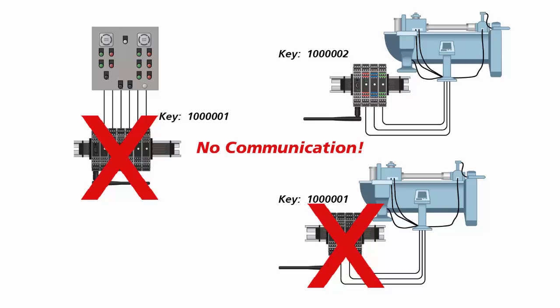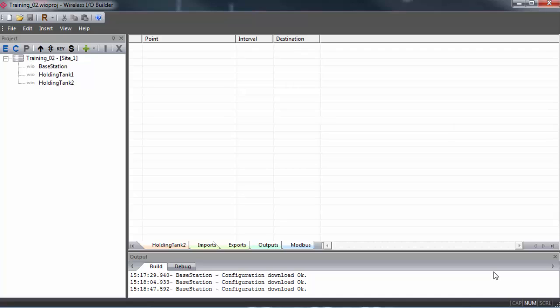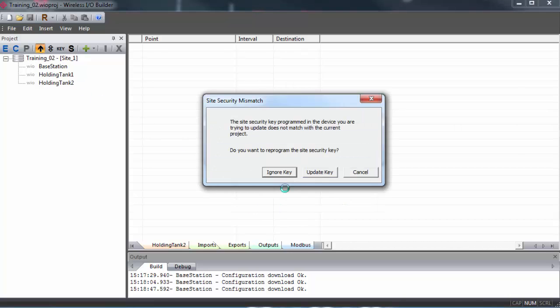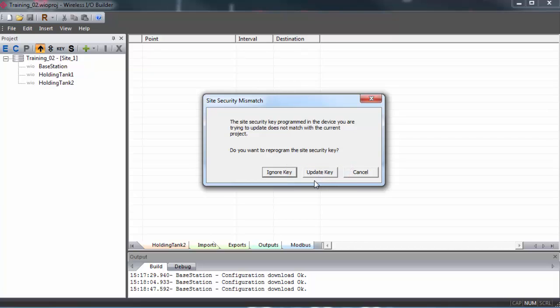So what you just need to keep in mind is that if you're setting up a gateway for the first time, whenever you hit update, it will update the file without incident. But if the gateway has been configured previously, you'll get a screen asking if you want to update the key or ignore it. If you're setting up a new network and are already planning on updating all of the gateways on the network, you should choose update since you want to use this new security key anyway. If, however, you have an existing network that's already up and running and you just want to make a change on the configuration of one of the gateways, you should ignore the new security key. That way it will continue using the old key that it already has and that all the other gateways on the network are still using and communication will go uninterrupted.